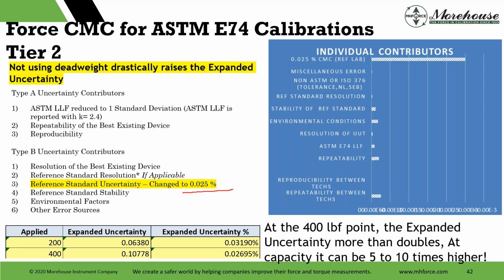That reference standard can impact things. This chart, or the other equation that I have that shows the contributions, you can just pick it off right there. What if I wanted to lower my uncertainty, my calibration and measurement capability? This chart says, hey, I need to find a better reference standard, a better reference lab. That's all it's telling me. If this is dominant, you could have a situation where something else is dominant and the reference lab's not going to do that much, and maybe you just have a bad instrument and you need to replace that instrument.